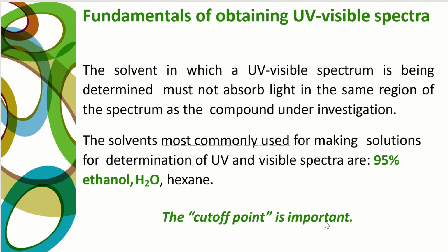The cutoff point is important, and by cutoff point we mean that we cannot have interference between the solvent and the sample where they absorb UV light. The cutoff point means that below that particular wavelength, the solvent absorbs. So after that point, everything that we see should be related to the sample and not the solvent.